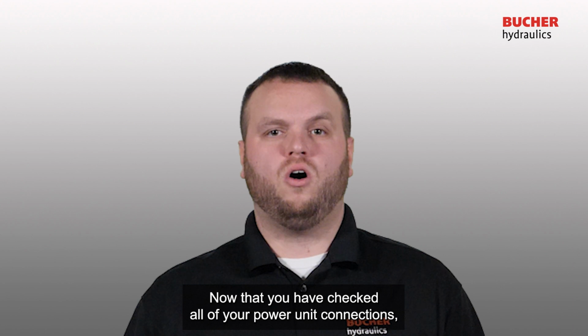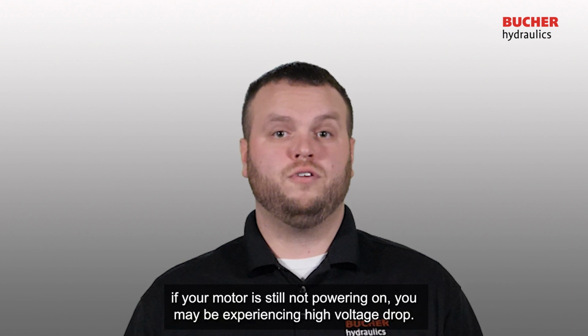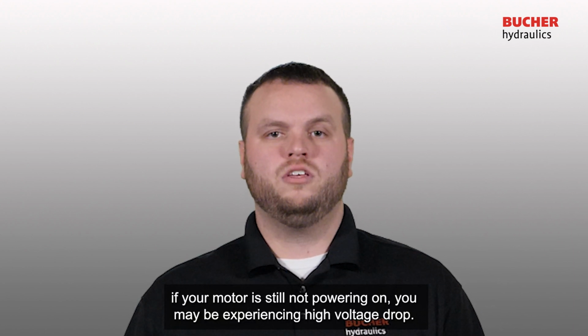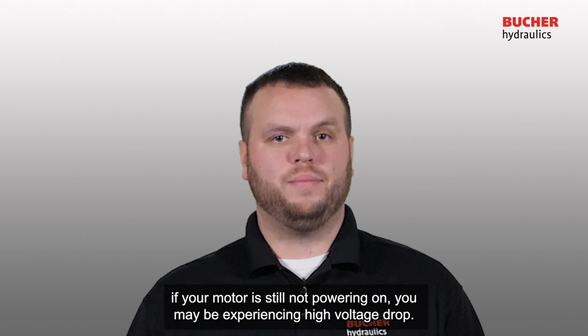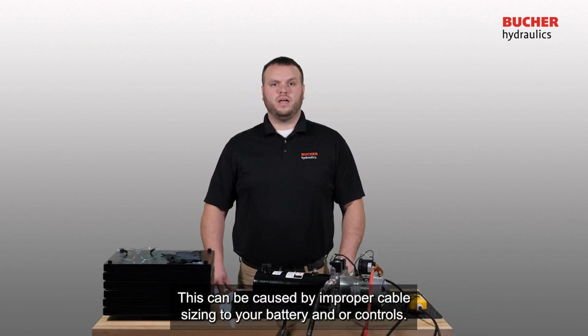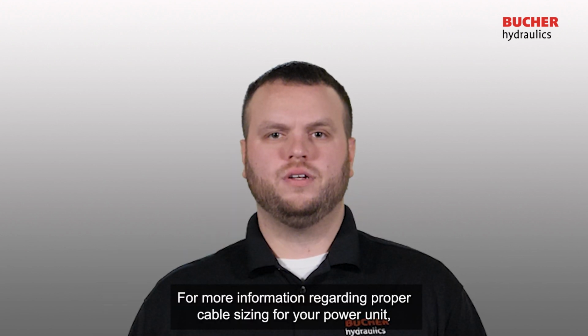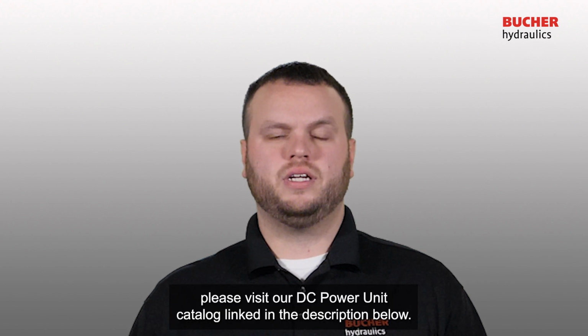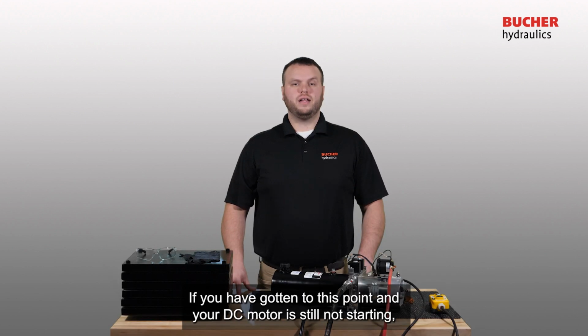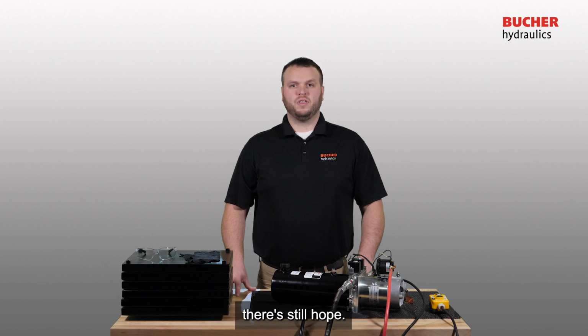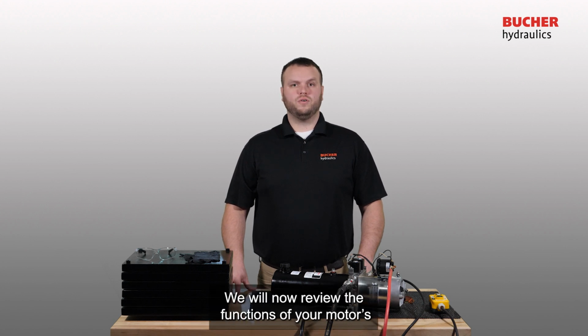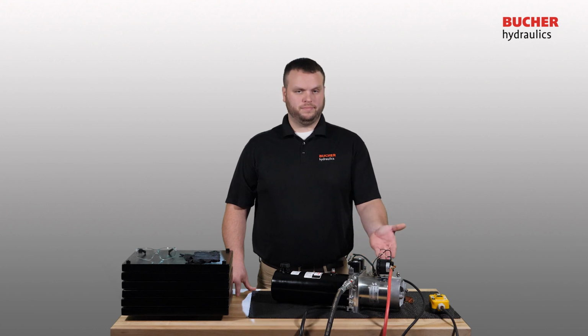Now that you have checked all of your power unit connections, if your motor is still not powering on, you may be experiencing high voltage drop. This can be caused by improper cable sizing to your battery and/or controls. For more information regarding proper cable sizing for your power unit, please visit our DC power unit catalog linked in the description below. If you have gotten to this point and your DC motor is still not starting, there's still hope. We will now review the functions of your motor's DC start relay.